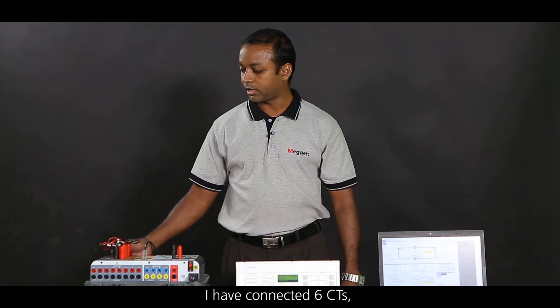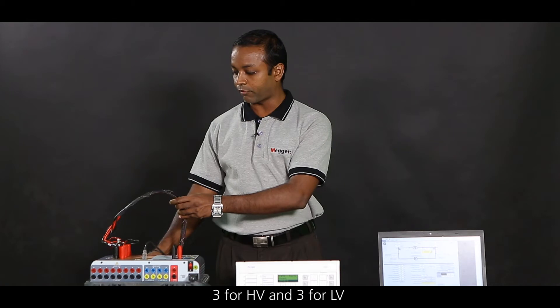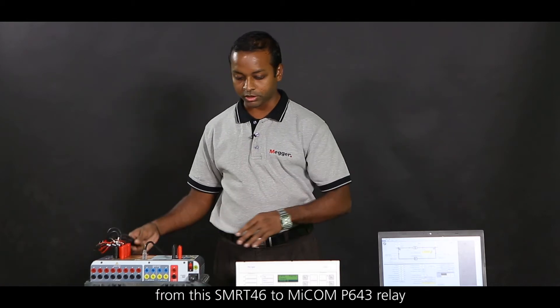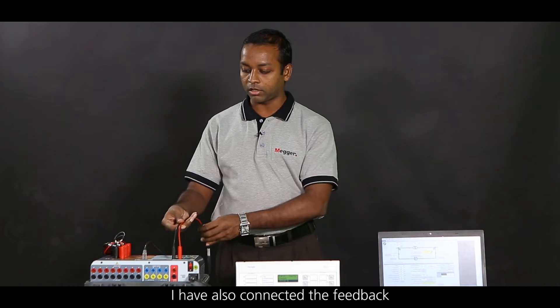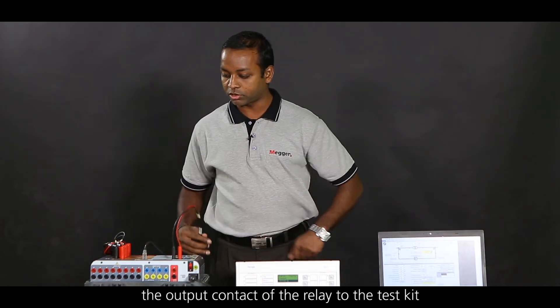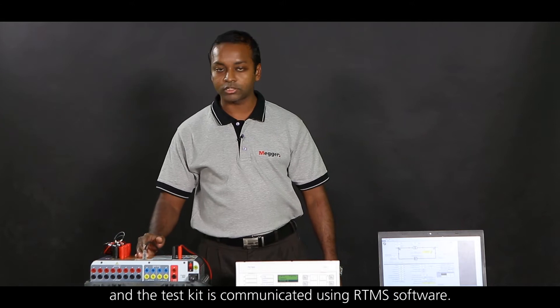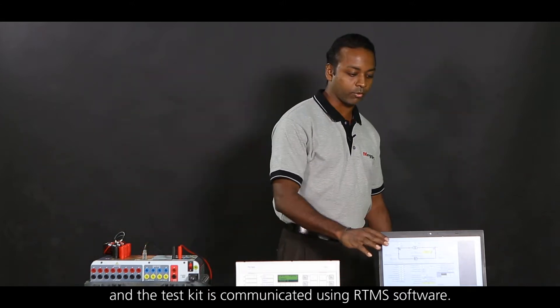I have connected 6 CTs, 3 for HV and 3 for LV from this SMRT46 to MiCOM P643 relay. I have also connected the feedback, the output contact of the relay to this test kit, and the test kit is communicated using RTMS software.